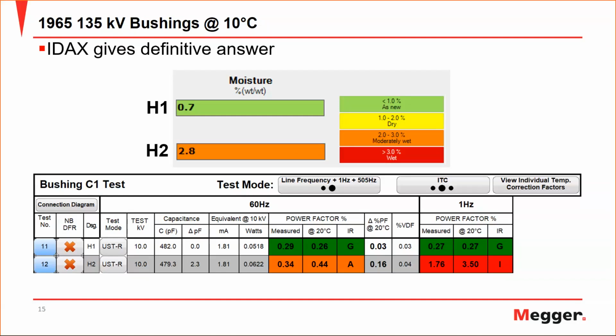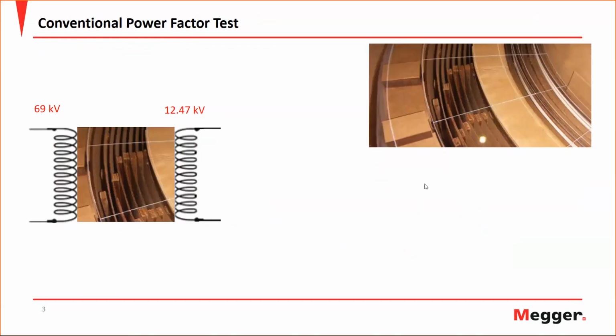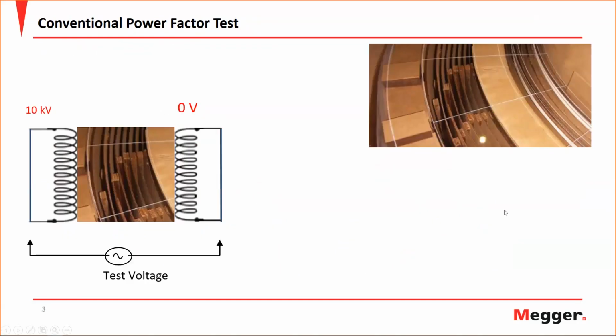So we're talking about during a power factor test, yes? He did not specify, so I'm assuming line frequency, since we're talking about line or power factor testing. If I go back to this slide here, when you short these together, you're not enabling the transformer to work anymore. So I think Diego will need to comment, you shouldn't have voltage on that other side. And further, if you have a YN, I don't think those need to be shorted together anyways. Just give me 1 second here so I can bring up my connection diagram.